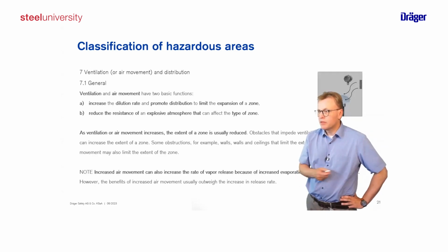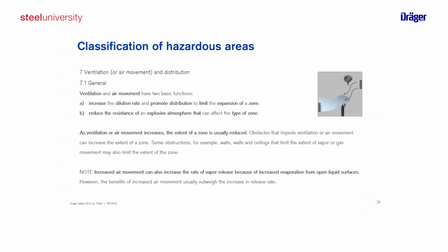Yeah, and so if, for example, you have ventilation, or your building is in an open design, you will always have the effect that the air which is coming into your room will either distribute, or with the air movement, at least it will dilute your explosive gas. So we have two basic functions we want to achieve with the ventilation. The one is we want to increase the dilution by adding or by moving the air. We want to dilute and bring down the concentration of the explosive atmosphere, and we want to avoid that the explosive gas is expanding in your plant or in the area. So we want to limit the extension.